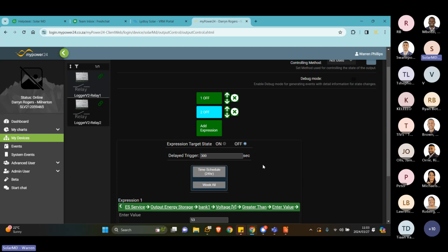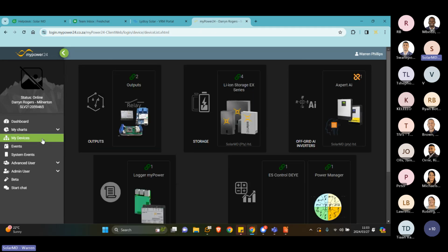I'm not going to go through the process of setting it up in the interest of saving time, but you can use voltage or state of charge as parameters to start your generator. In some cases customers do very basic things, like if the battery's running low, they have the relay close, which activates a light, closing a circuit so the big red light in their lounge turns on. Some people choose to do that - just one simple example of how people use the relays.